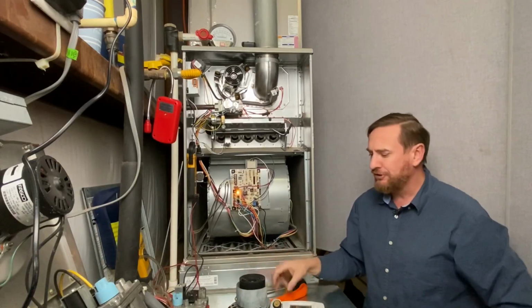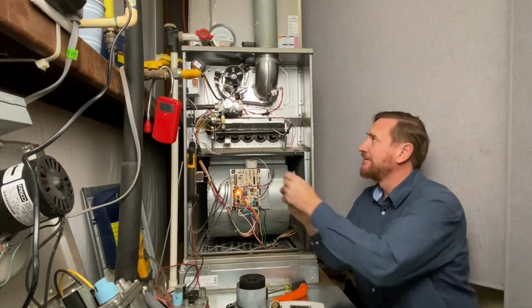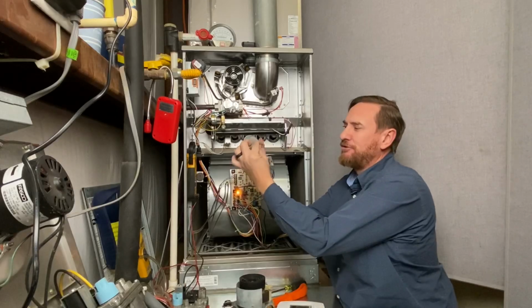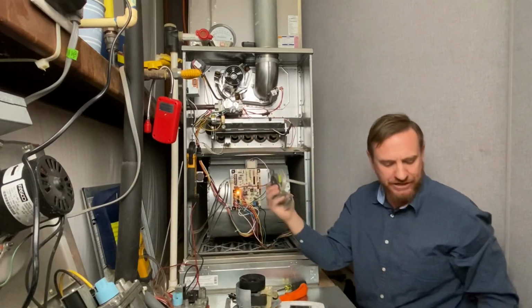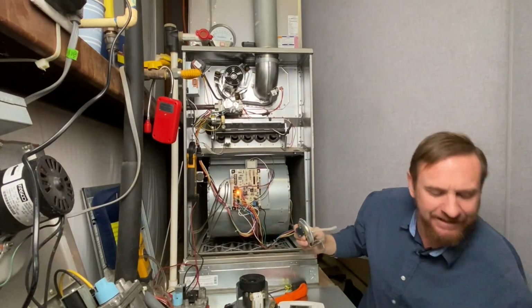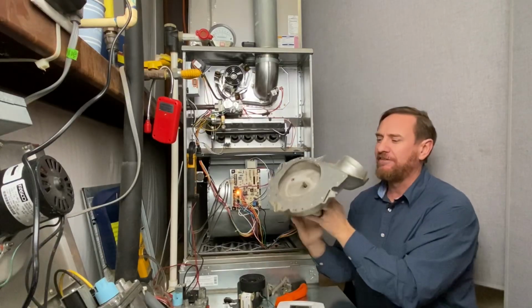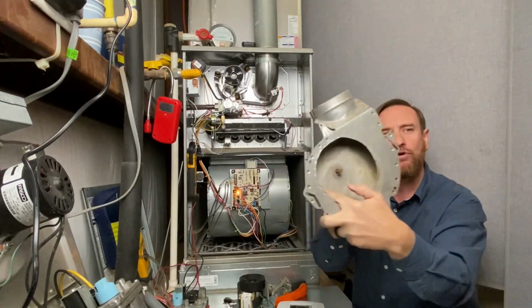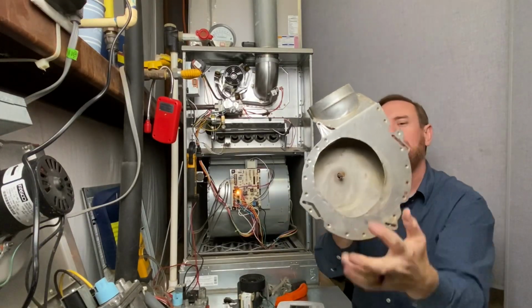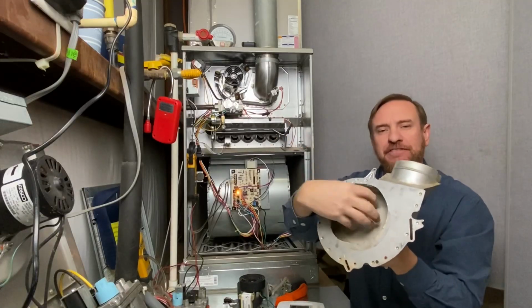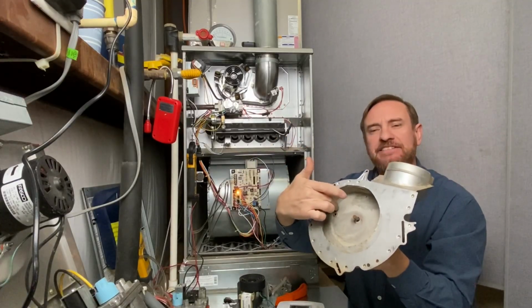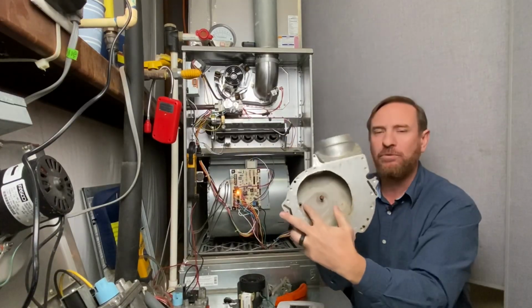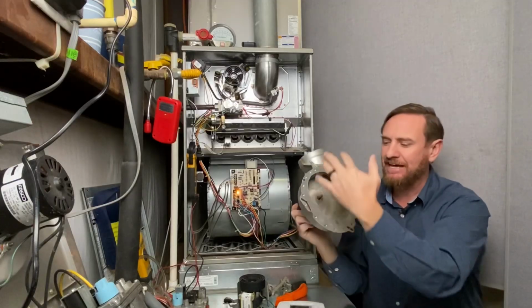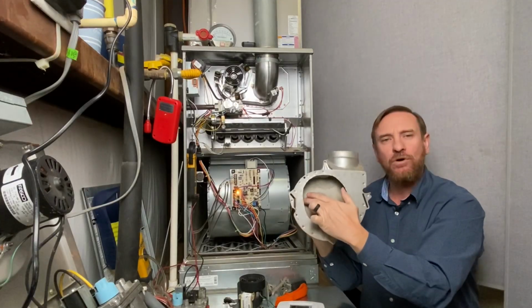And as it pulls a draft through the heat exchanger, it's also pulling a draft through this little tube to the pressure switch. Now if we look inside of this motor, I've taken the wheel off of this one, and you can see this little hole right here. That little hole is where it's pulling the draft through. The fan blade's been removed and it's pulling a draft. It's negative pressure. On this particular one, it's corroded up. So this has had moisture coming into it.